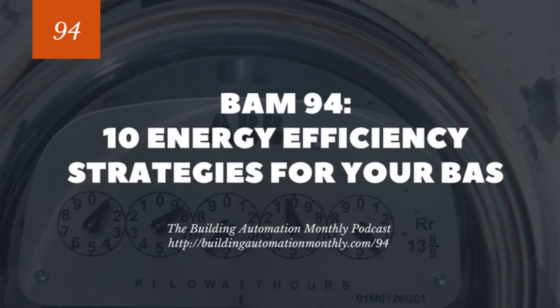Now, how do you check for these things? Well, you need to have trends, first off, and you have to have trends at a decent interval. Typically, the 15-minute interval won't cut it for this, especially if you have oscillating valve actuators, meaning they're opening and shutting rapidly. In this case, you may want to go to change of value trends, where if it changes by more than 5%, you log that trend value. In this case, you'll be much more likely to see the heating and cooling happening at the same time.